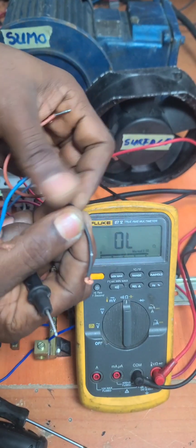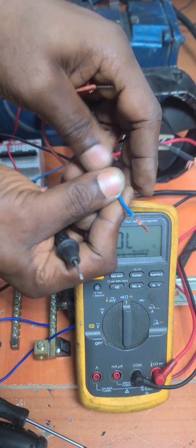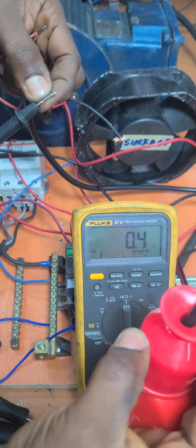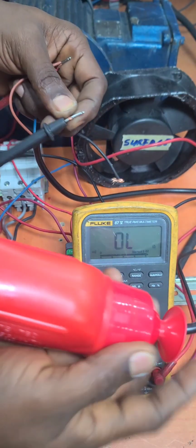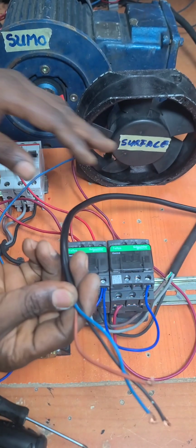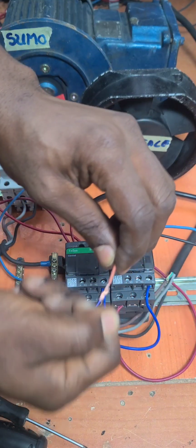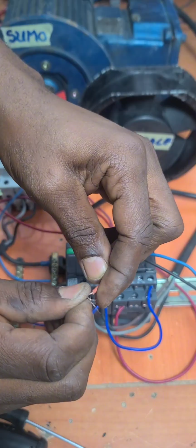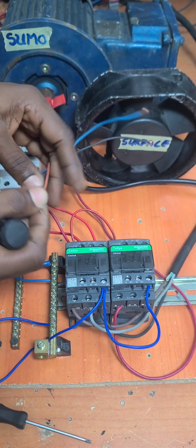So this black is going to serve as our high level switch, while this blue is going to serve as our low level switch. This way is off, and when the water level goes low and this is pointing down, you are going to hear that beep. All right, so we keep this out of the way. Take this one out of the way, and then we're going to make use of only the wires from our float switch. So we're going to now get power on this one by connecting it to L1, L2, or L3, anyone we want. But let us connect it to L1.